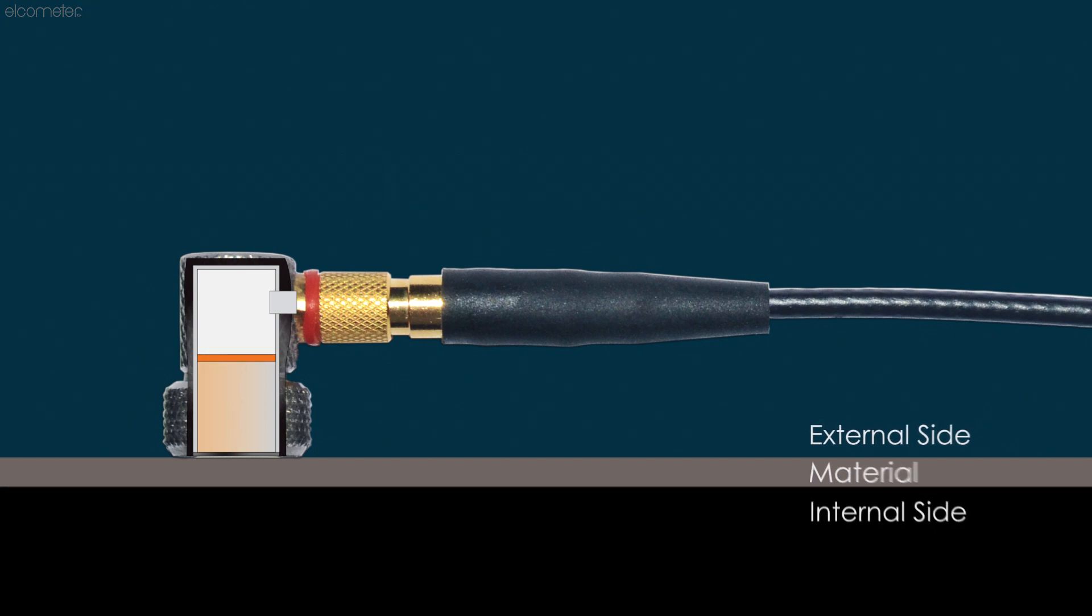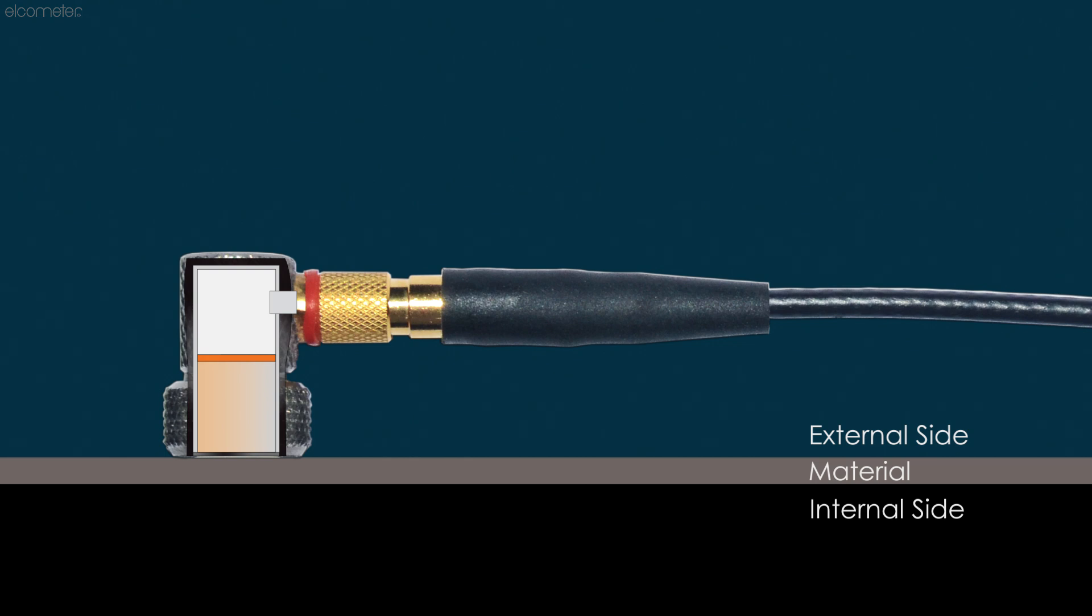However, measuring thin materials means that the ultrasonic signal will return to the transducer incredibly quickly, and as a result there's not always enough time between the pulse leaving the element and the echo returning. This is why, when using an Elcometer PTG...